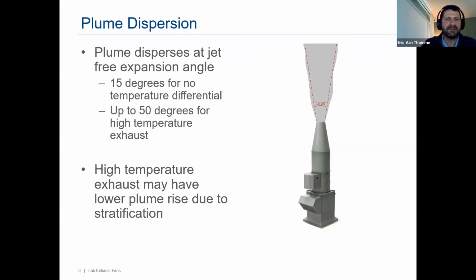Talk real briefly about plume dispersion. I briefly mentioned it before. One of the fan applications is generator exhaust. Depending on the proximity of the generator to the laboratory fan, you may have a high temperature situation there. That high temperature exhaust airstream may result in a lower plume rise due to some stratification, and the amount of that stratification and the angle of the plume is going to vary depending on that temperature.